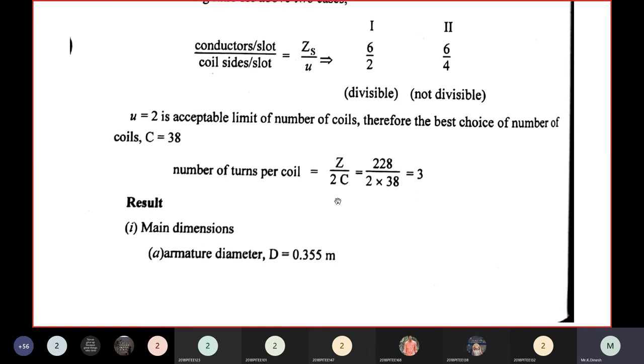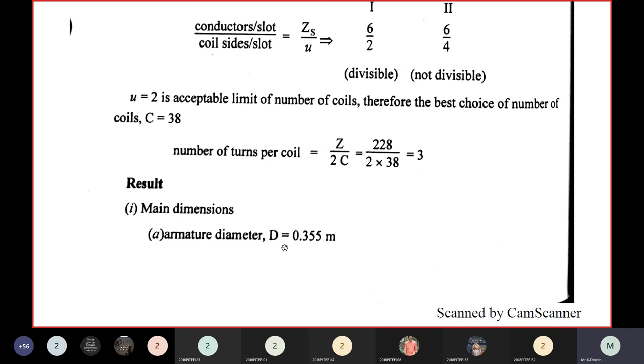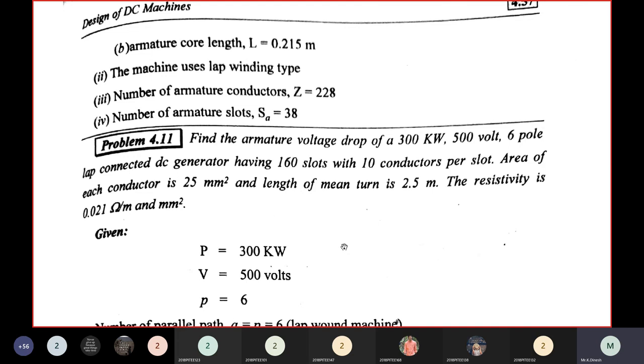Final results: armature diameter D = 0.355 m, armature length L = 0.215 m, winding type is lap wound, number of armature conductors Z = 228, number of armature slots SA = 38.